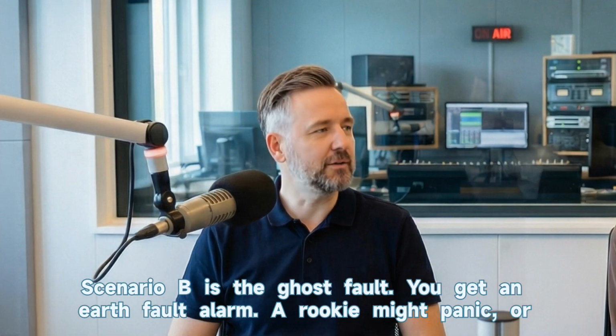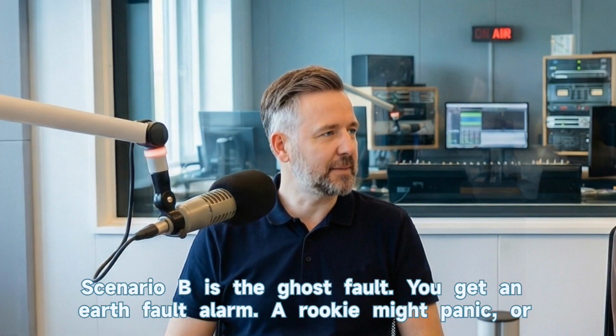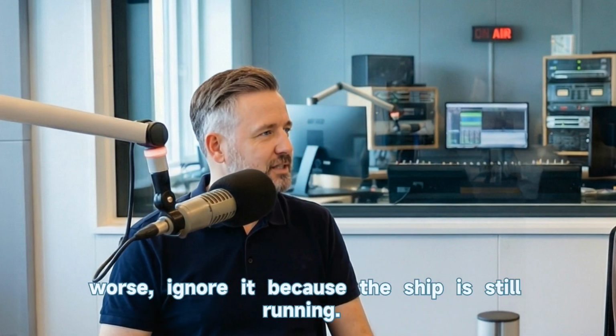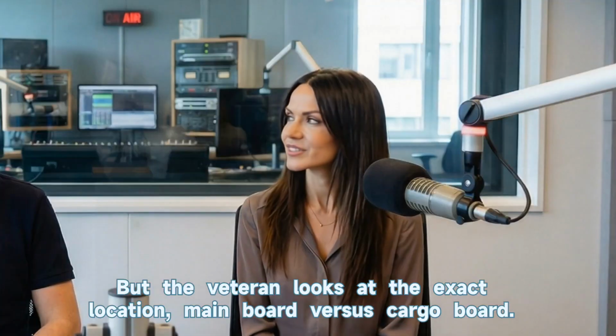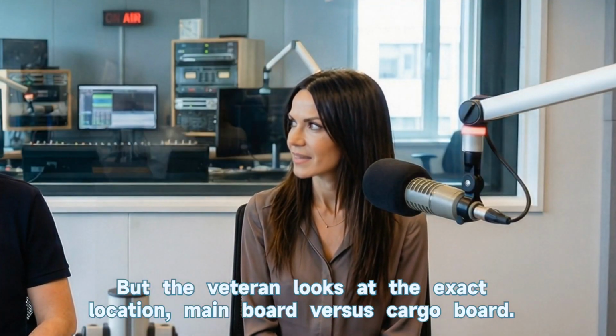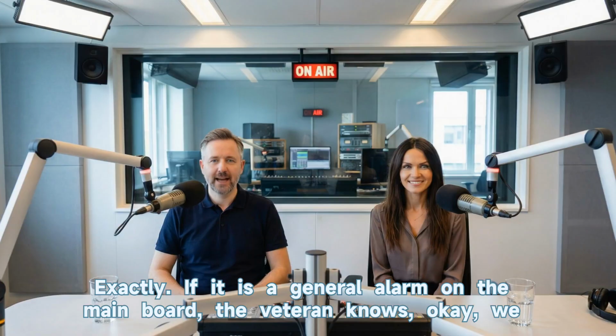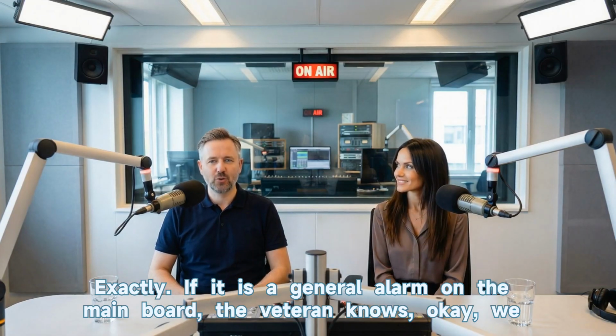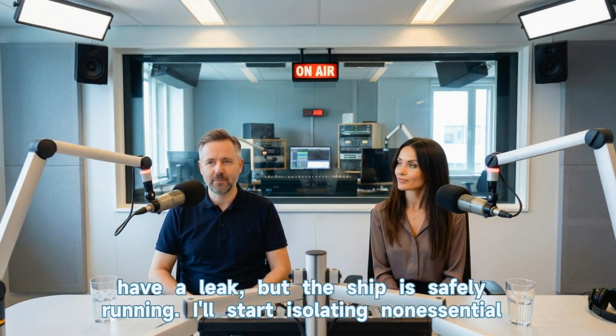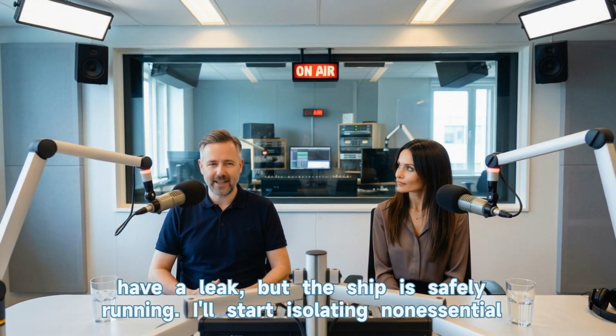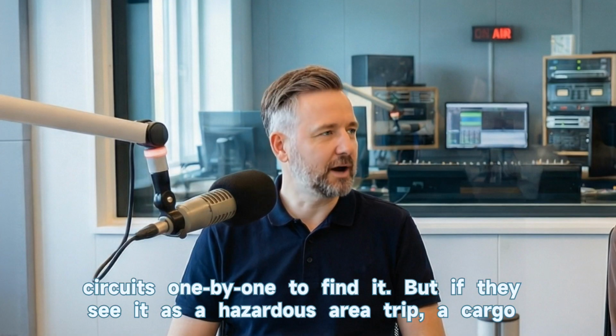Scenario B is the ghost fault. You get an earth fault alarm. A rookie might panic, or worse, ignore it because the ship is still running. But the veteran looks at the exact location. Main board versus cargo board. Exactly. If it is a general alarm on the main board, the veteran knows, okay, we have a leak, but the ship is safely running. I'll start isolating non-essential circuits one by one to find it.